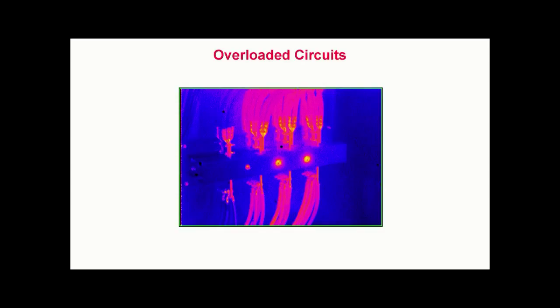Overloaded circuits. This thermogram shows excessive heating caused by an overloaded circuit. Overloads are characterized by uniform but excessive heating throughout the entire length of the conductor. Here, we see all of the conductors operating at the same temperature. However, they are warmer than they should be.